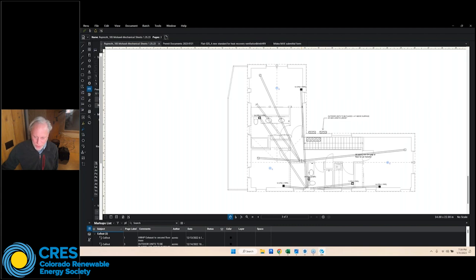Upstairs, we're actually using a very simple bath fan in the central core of the space, providing a little extra boost into each of the rooms, downstairs and upstairs. We'll also be able to calibrate each of those ducts into each room to make sure they're getting sufficient heating or cooling based on where they are.